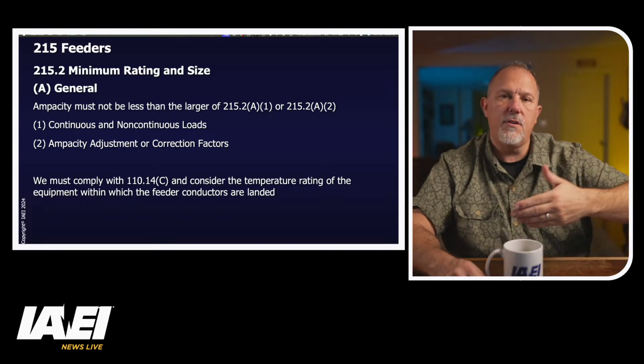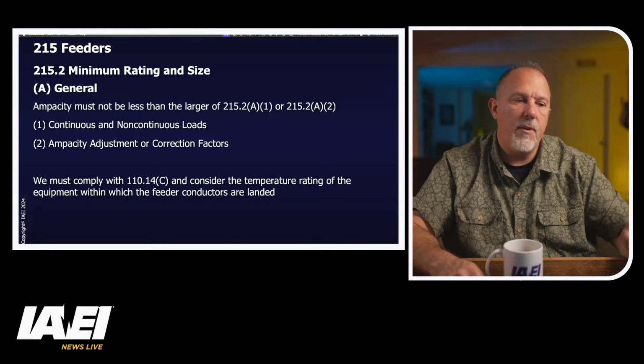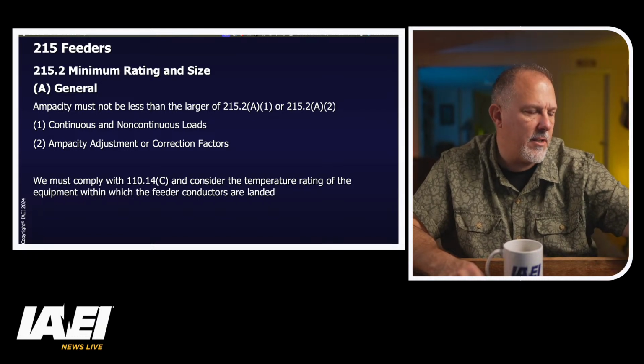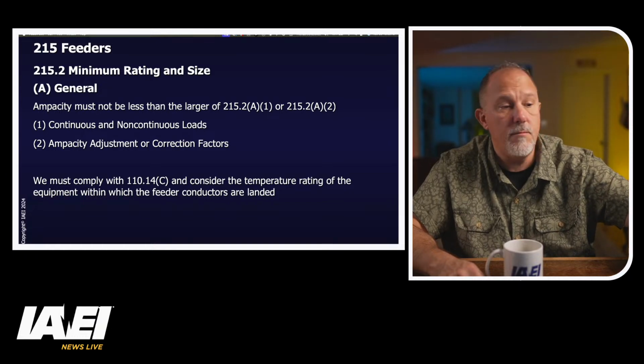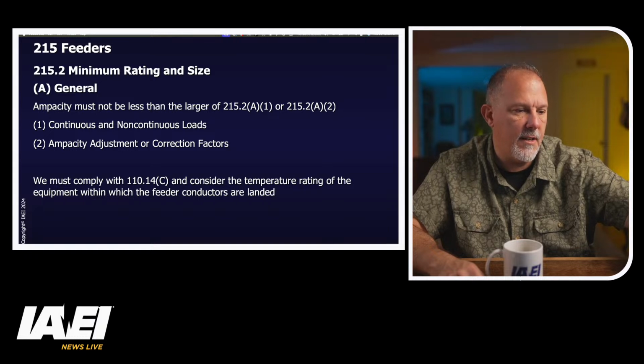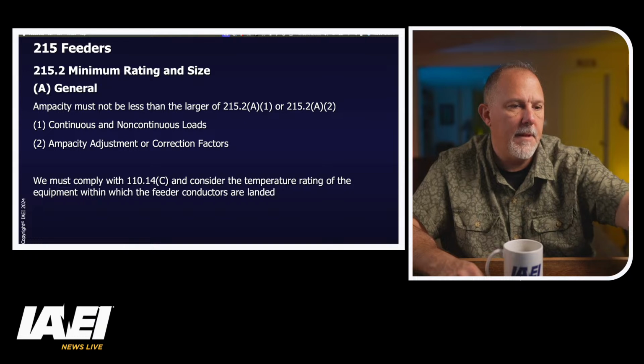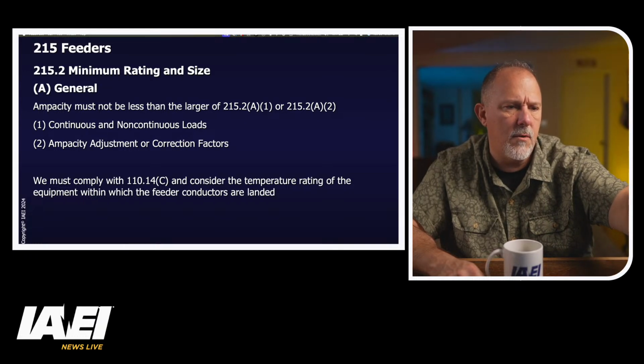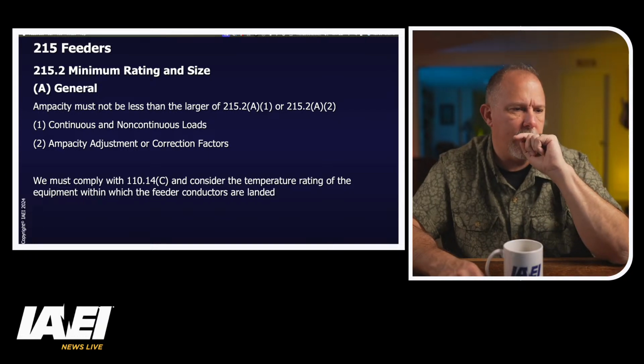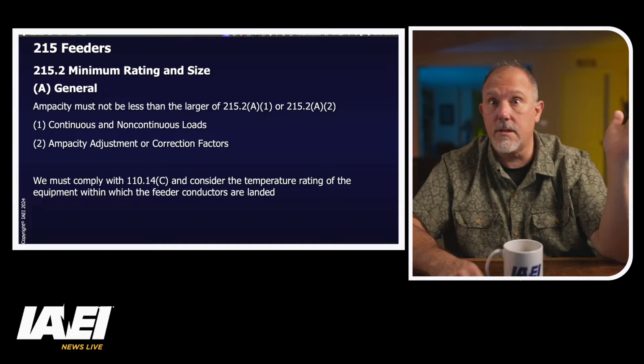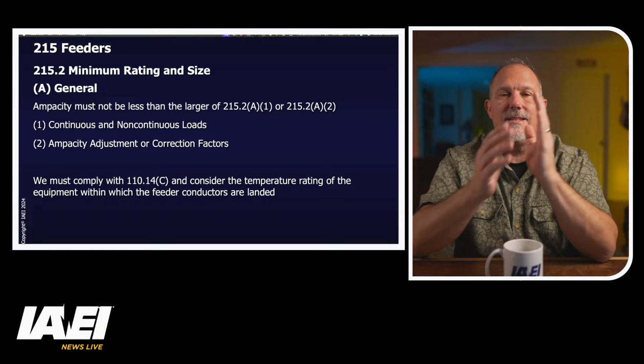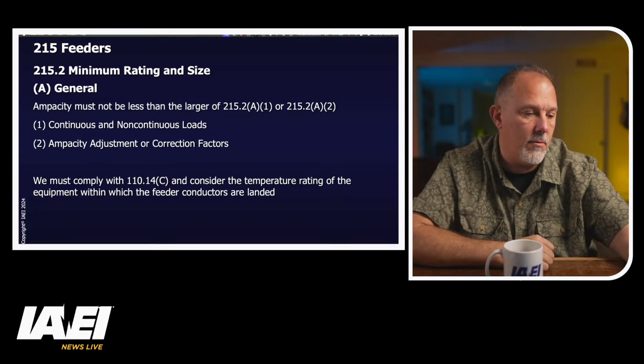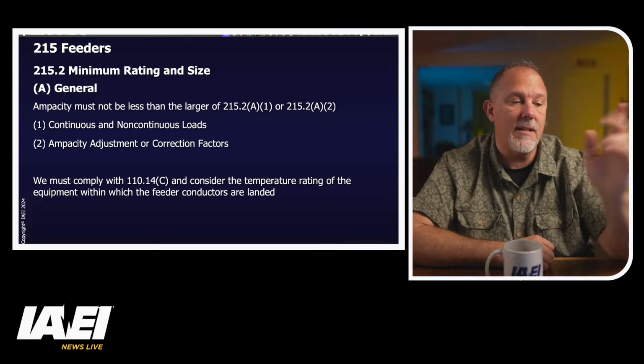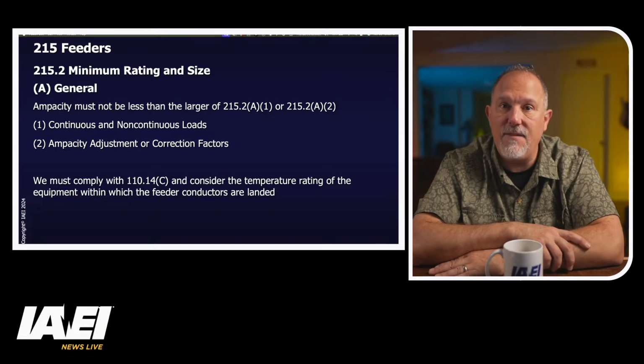So then what we do is we go to 310, and we find 175 amps. Let's go to 310.16. I said I needed 175, right? So I'm going to do expand table. 175. Oh, and I can pin the header. Just learned that not too long ago. And since I'm dealing with a 90 C insulation, I scroll down and I find that I'm into a 2-aught conductor, which can handle 195 amps.